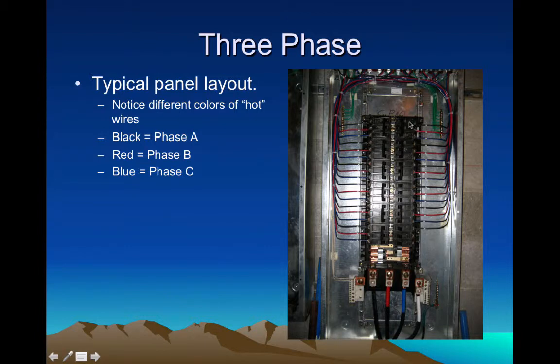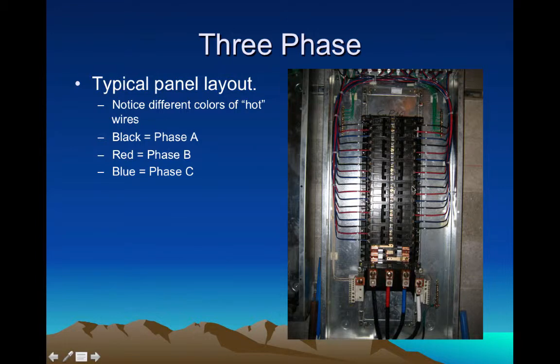You would want to see Phase A, Phase B, Phase C, Phase A, Phase B, Phase C. If you're having any weird interference or digital sync problems, that might be something to look at — making sure the electrician wired all of the outlets in a given studio on the exact same phase of your specific room or studio.